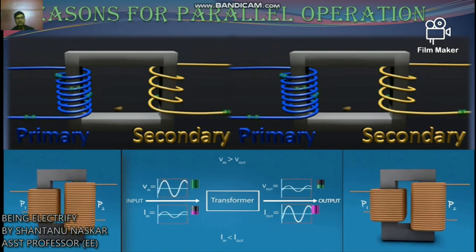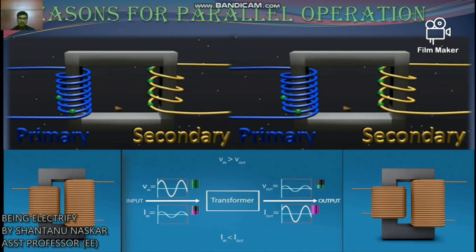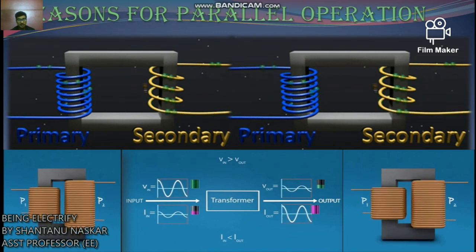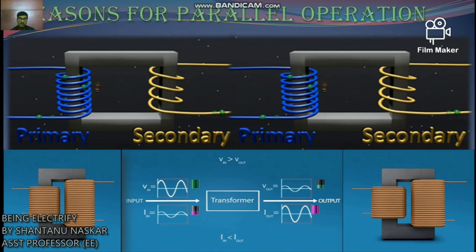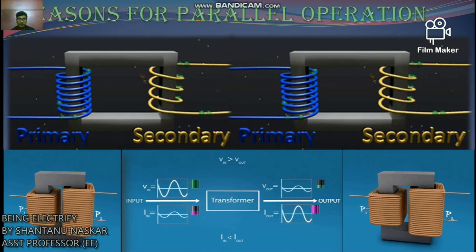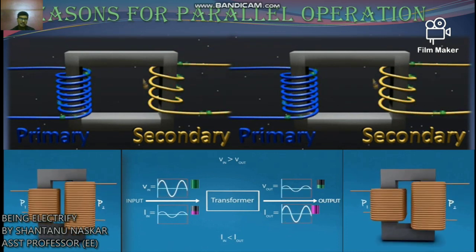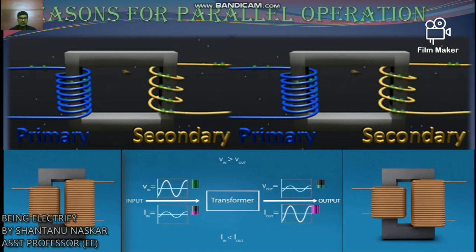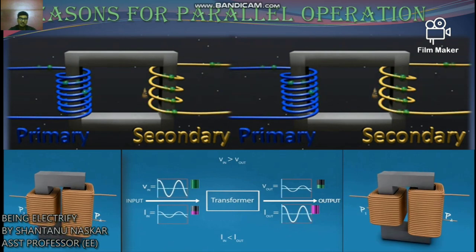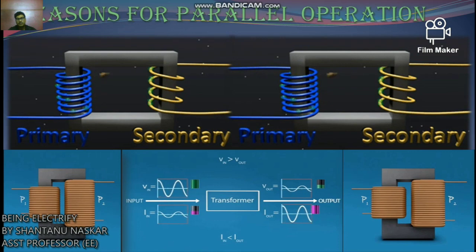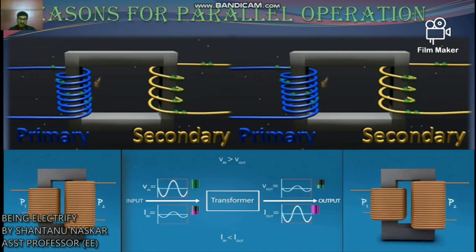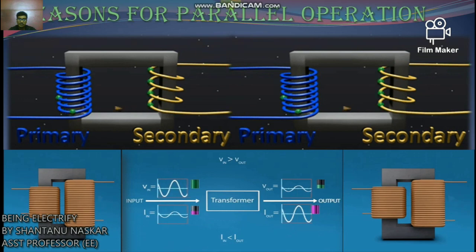In a substation, the total load may be supplied by an appropriate number of standard-size transformers, reducing spare capacity. Parallel connection also allows future expansion of the substation beyond the capacity of already-installed transformers. If any transformer in a parallel system breaks down, there will be no interruption of power to essential services. Similarly, if any transformer is taken out for maintenance and inspection, continuity of supply will not be disturbed.